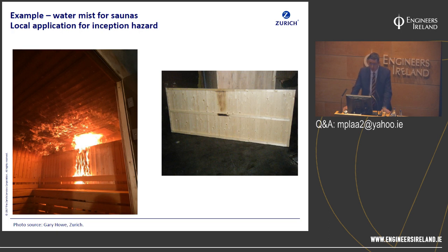And here's an example on the right of one of my test pass-fail criteria for my fire test was that the fire mustn't break out of the sauna compartment itself. And that was the only damage to the sauna when the water mist system activated. So I ripped apart the sauna, took it apart, analysed the damage, and that's the only damage we had. So it proves it's an effective solution for a small combustible risk like that.